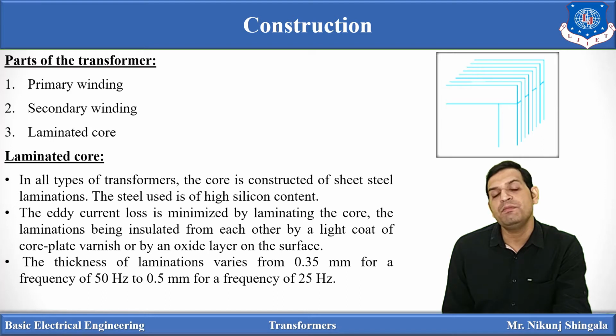The thickness of the laminations depends on the frequency of the operation. If the frequency is 50 Hz, then the thickness of the lamination should be 0.35 mm, and if the frequency is 25 Hz, then it should be 0.5 mm. So basically, a laminated core is made up of sheet steels. It consists of a number of sheet steels which are insulated from each other by means of some oxidation layer.